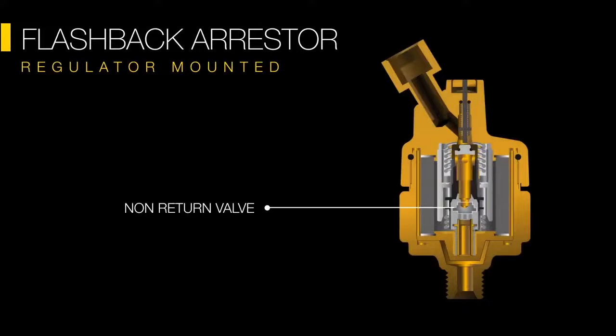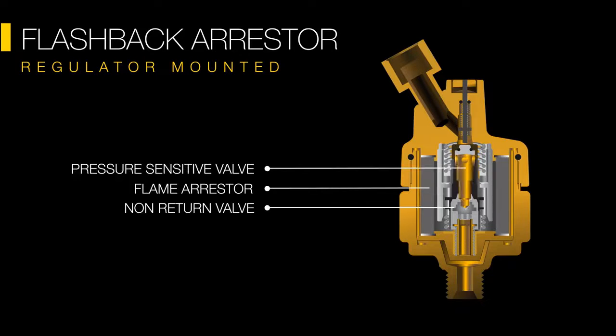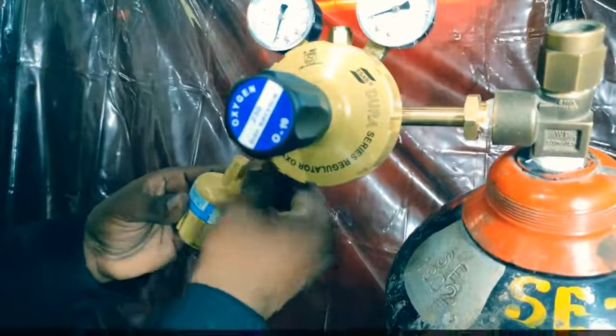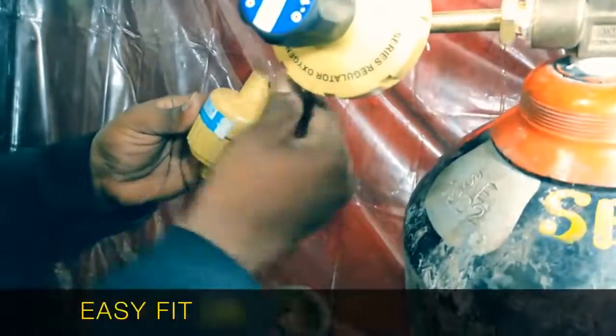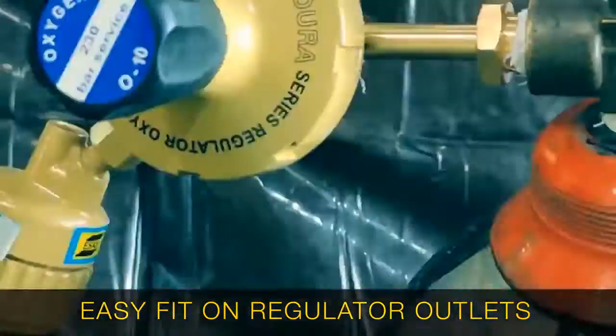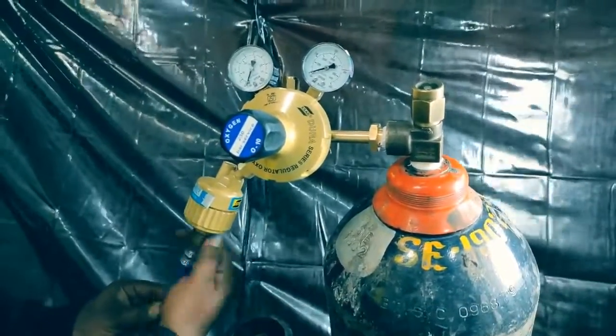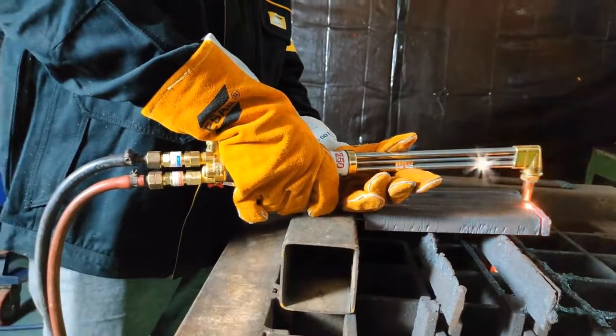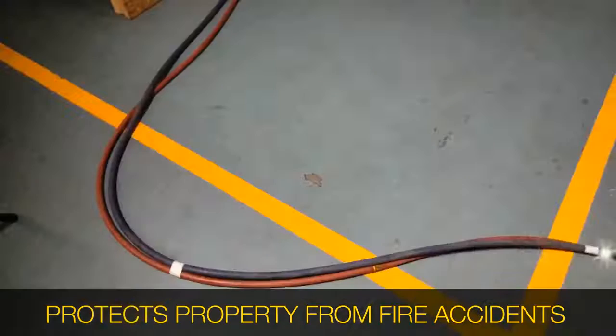Regulator mounted flashback arrestors provide three to four-level protection, incorporating a non-return valve, flame arrestor, pressure sensitive cut-off valve, and temperature sensitive cut-off valve. They fit easily into the regulator outlets with a range of connections suited for different gases and cylinder designs, protecting your property from catastrophic fire accidents and explosions that could occur through flashbacks.